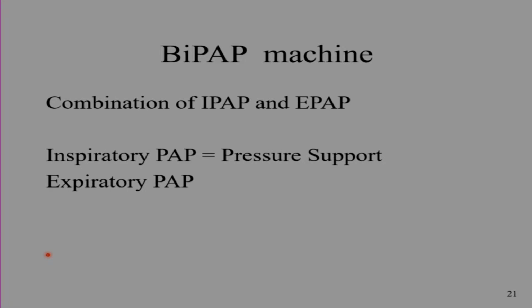It's a BiPAP, bi-level positive airway pressure machine, a combination of IPAP and EPAP. IPAP is inspiratory positive airway pressure, and EPAP is expiratory positive airway pressure. The inspiratory pressure is always higher than the expiratory pressure.